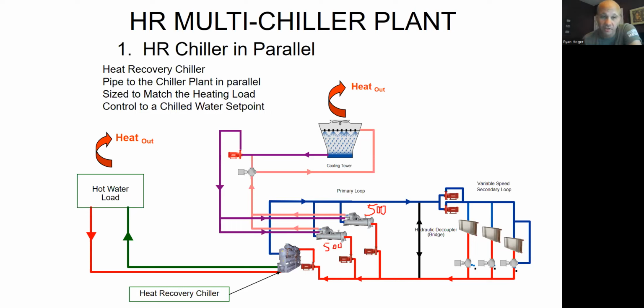And then this chiller down here is sized for whatever the heating load is. That could be domestic water, showers, laundry for like a condo or apartment building. It could be swimming pool stuff. It could be an office building where I've got to heat the perimeter. So whatever my hot water load is there, and maybe that equates to 300 tons, that guy will be sized for that, and he'll be running for that.